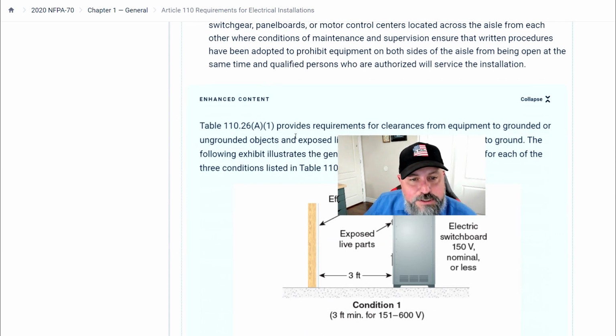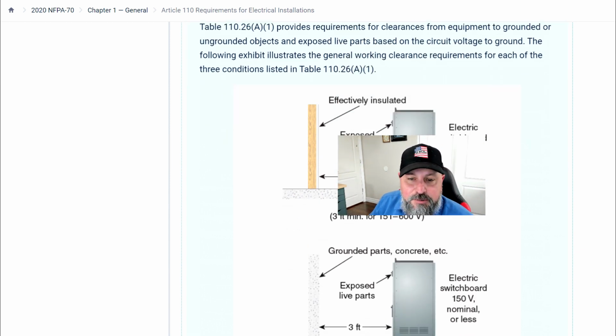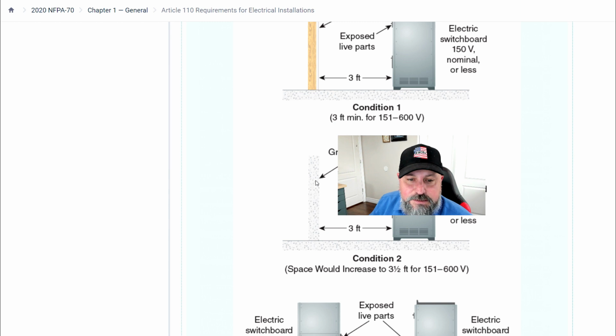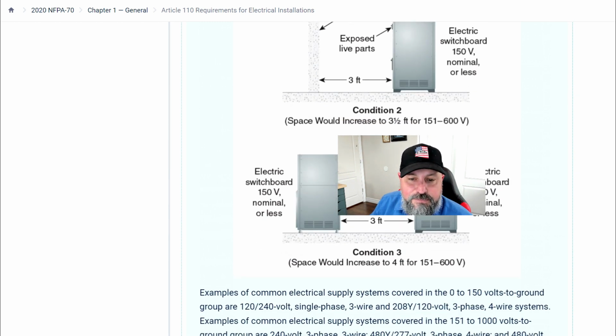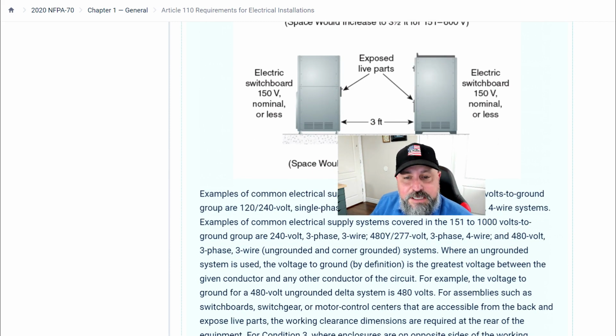So Table 110.26(A)(1) provides requirements for clearance from equipment to grounded or ungrounded objects and exposed live parts based on the circuit voltage to ground. The following exhibit illustrates the general working clearance requirements for each of the three conditions listed in the table. So we're just going to show this again. 150 nominal or less, condition 1, 3 feet, insulated. Grounded concrete, right here, 150 or less, 3 feet. Condition 2, 3.5 feet for 151 to 600, 3 feet. Condition 3, space would increase to 4 feet for 151 to 600 volts.